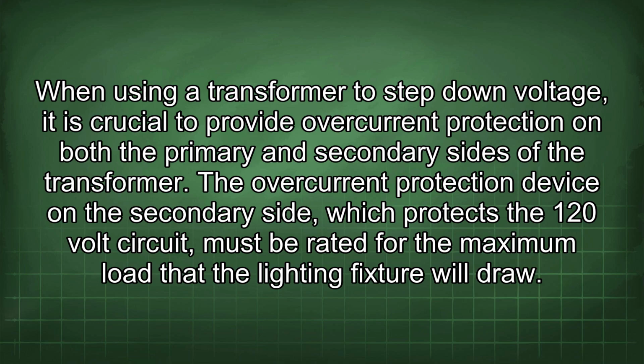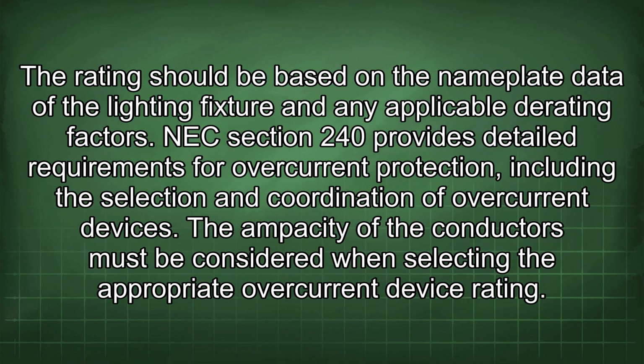When using a transformer to step down voltage, it is crucial to provide overcurrent protection on both the primary and secondary sides of the transformer. The overcurrent protection device on the secondary side, which protects the 120-volt circuit, must be rated for the maximum load that the lighting fixture will draw. The rating should be based on the nameplate data of the lighting fixture and any applicable derating factors.